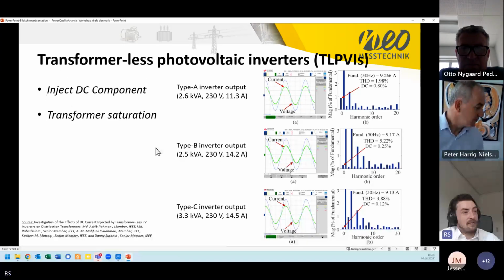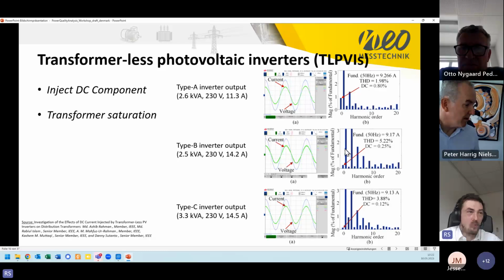What we see here in the FFT is that there are different types of it. It doesn't really depend on the power itself or the current, but they inject a DC current into the grid. A DC current is not so good for our electrical equipment in the field. For example, our transformer stations will go into saturation, and this could be problematic. They get lifetime reduction, they heat up, they have real problems with this, and at the end they get damaged.